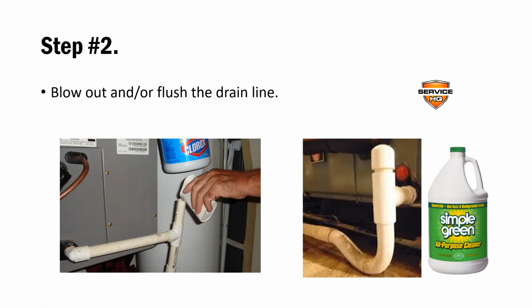So the drain line is connected to your evaporator coil, and it needs to be cleaned periodically. It needs to be flushed periodically. So what you can do is, once every month or two, take a half cup of bleach or Clorox and dump it down that line. And that's going to keep, if there's any standing water in that line, which there shouldn't be, but once in a while there is, that's going to keep any algae from growing in that line, which creates clogs. And you do not want that to happen.